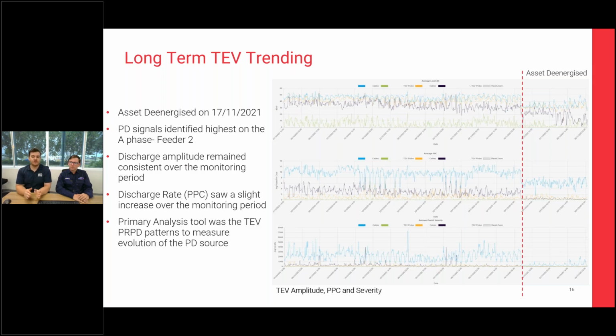If you look at the right of the plots, you can see how significantly all the amplitudes of this feeder dropped the second the asset was de-energized. That gave us a lot of confidence that we'd located the right asset, because if we de-energized and they didn't all disappear, we probably would have made the wrong call.